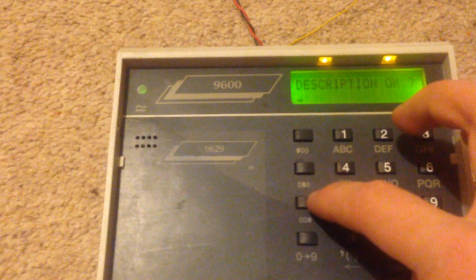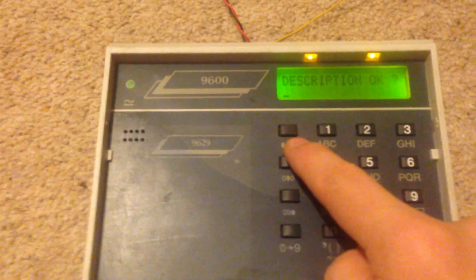So I'm in engineer's menu and it asks me to program a zone, so I say yes, and I'm going to program zone 01. Yes, and I want the zone to be used, and the description is not okay. So at this time I fit the overlay and then I press no, and then each of these keys here, you have to press this and then press one of these keys. So this does the first digit.